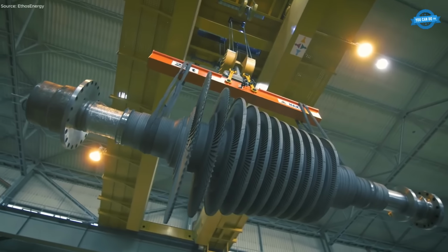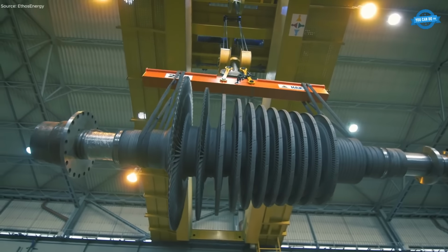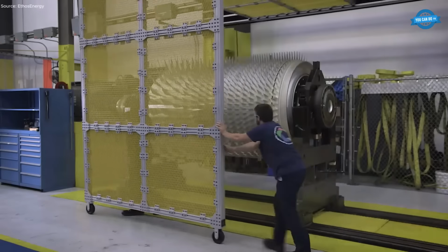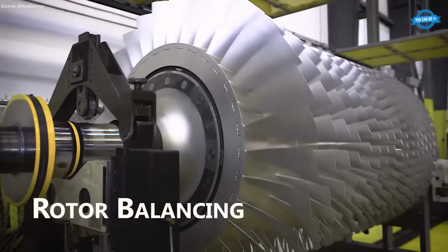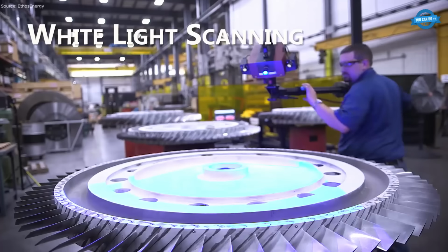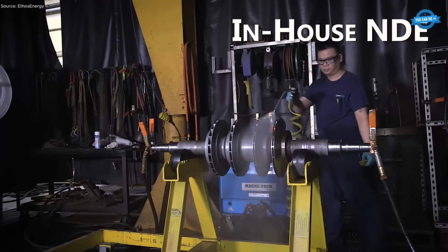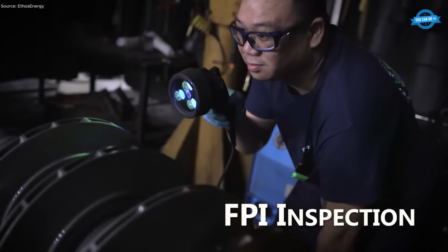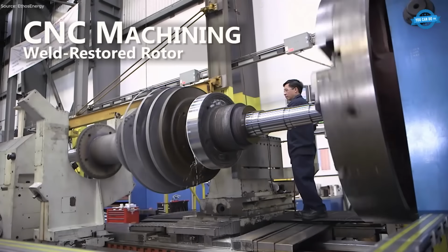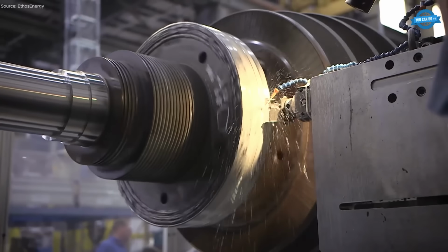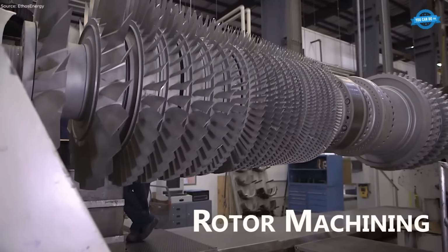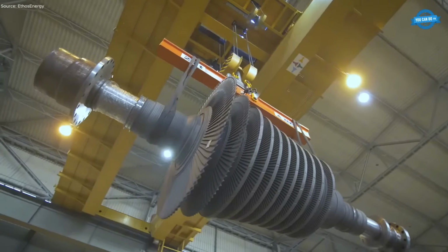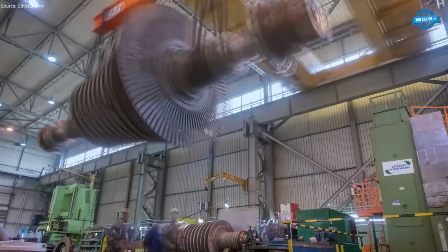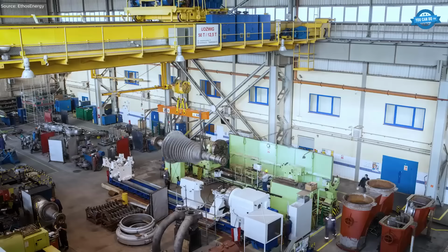The maintenance and overhaul of a steam turbine follow a structured sequence of inspections and machining operations to restore performance and ensure safe operation. The process begins with rotor balancing, where any mass imbalance is corrected to prevent excessive vibration. This is followed by fluorescent penetrant inspection, FPI, used to detect fine surface cracks that cannot be seen by the naked eye. The rotor then undergoes precision machining, while ultrasonic testing is applied to identify subsurface flaws within the material.